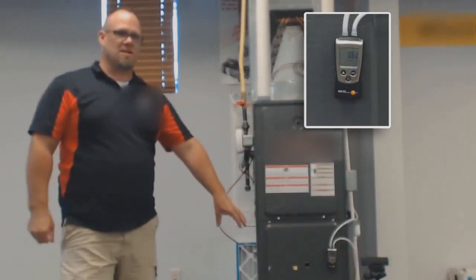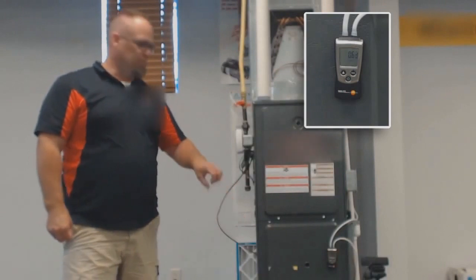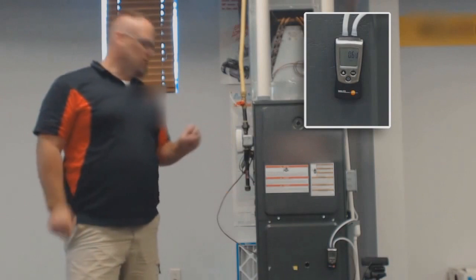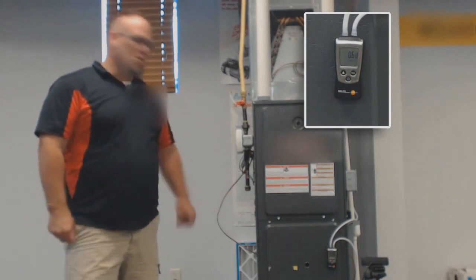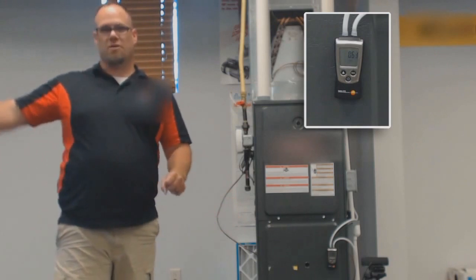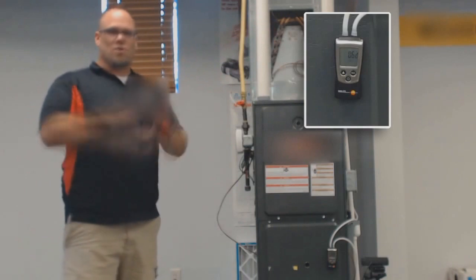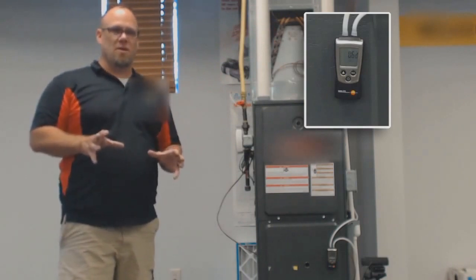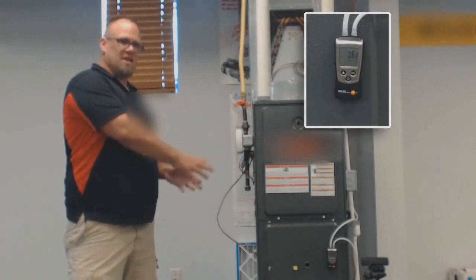And all we've talked about here is setting up the blower. If the blower's not set up right, nothing else will function correctly. We still have to have the proper size filter. We have to have the proper type of filter. Our charge has to be good. Our ducts have to be clear and open. We have to have enough return air. There's a lot of stuff that goes into this, but it all starts with the blower. If the blower is set up properly, you can work with everything else.